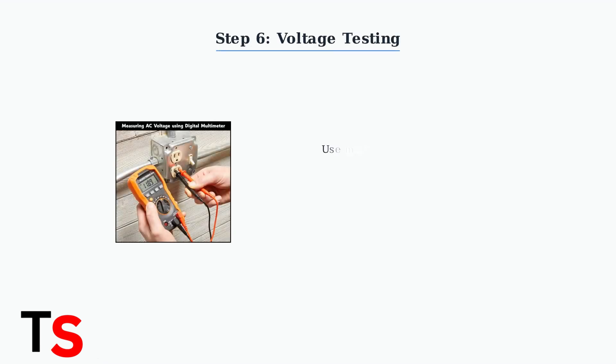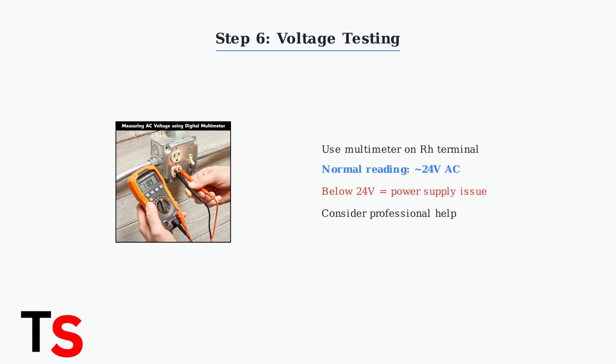Use a multimeter to check the voltage at the RH terminal. A reading significantly below 24 volts indicates a power supply problem that needs professional attention.